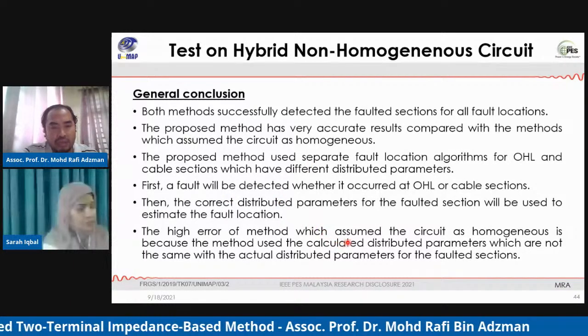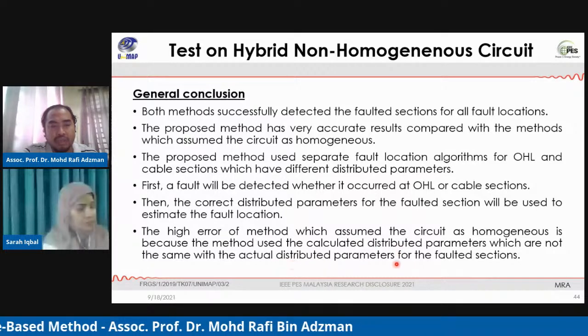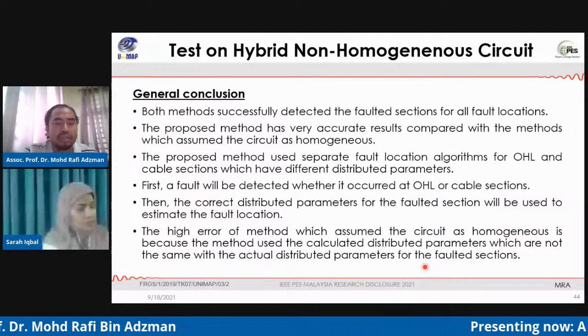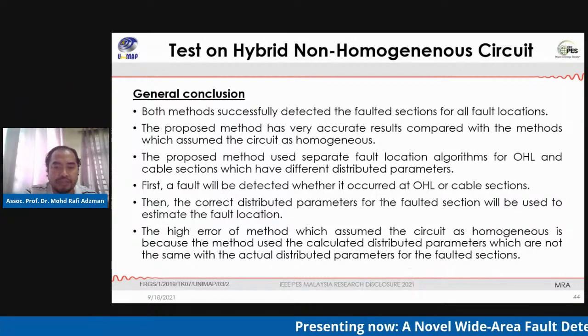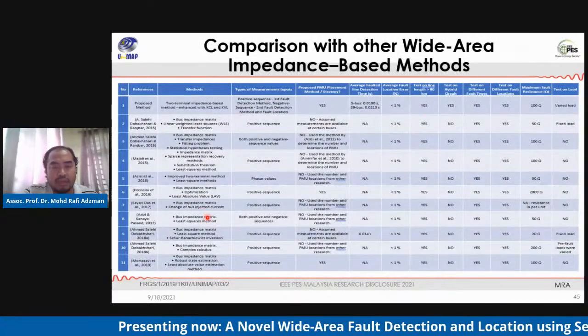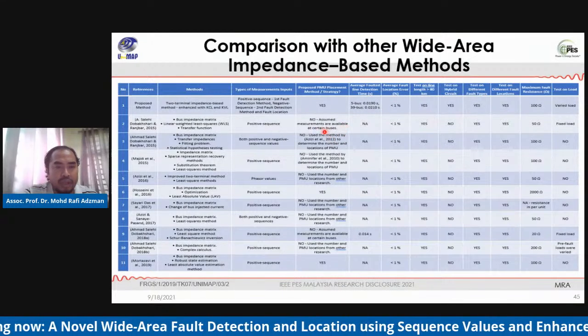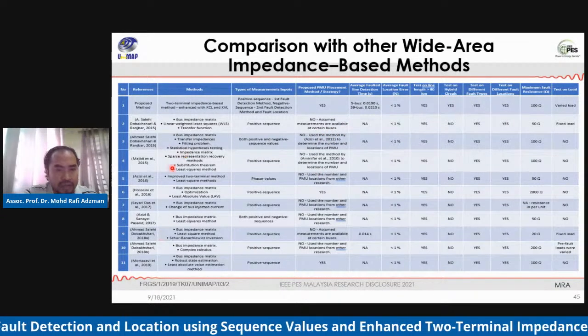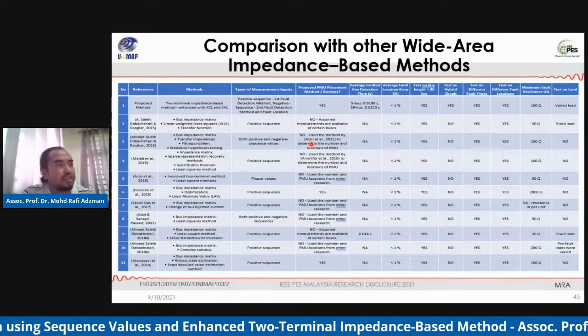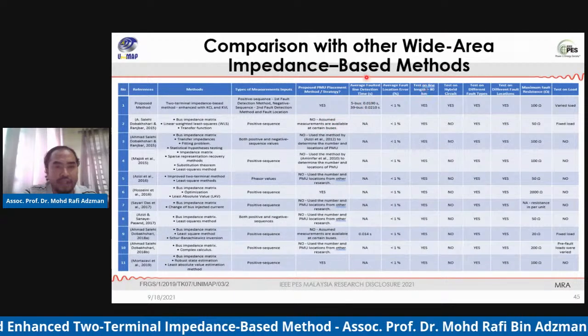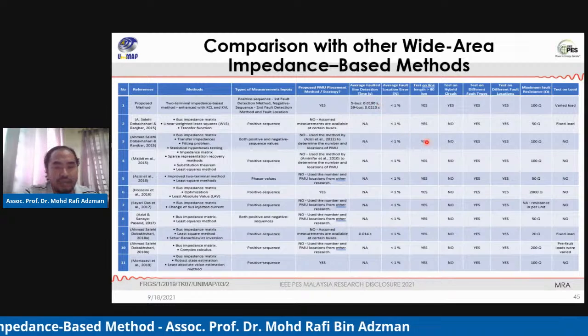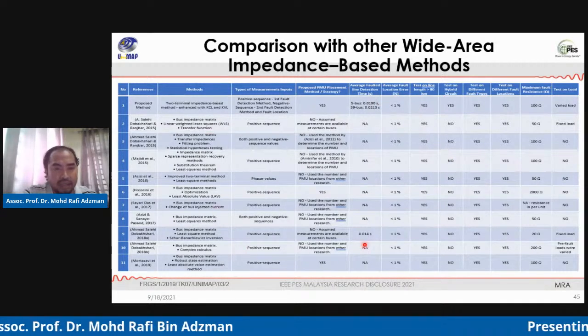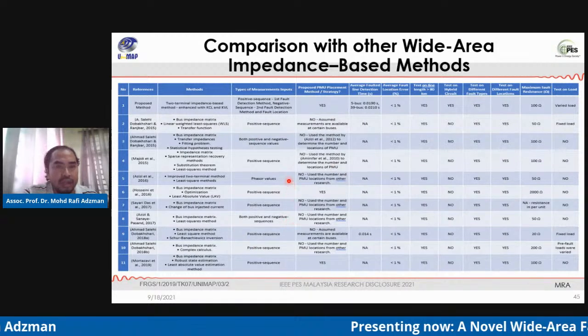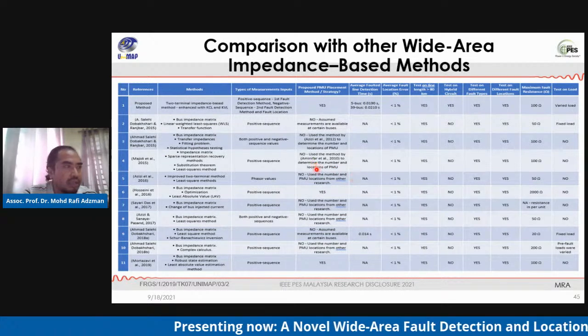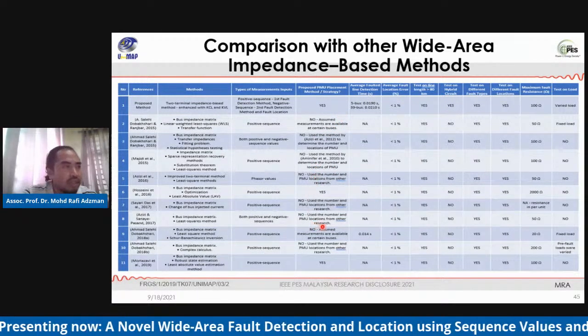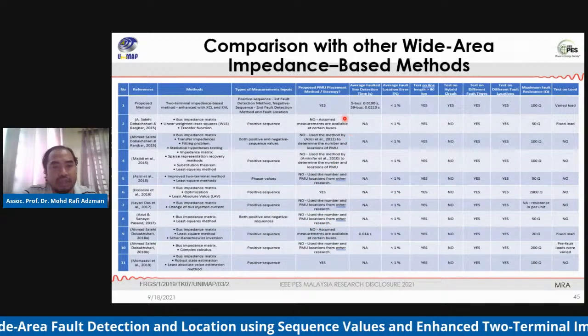The higher error of the method which assumes the circuit as homogeneous is because the method uses the calculated distributed parameter, which is not the same as the actual distributed parameter for the faulted sections. From this work, we have compared with at least 10 reference literatures, and we compare the types of measurements, the proposed type of placement, and the average faulted line detections, and we can say that it is on par with all the other researchers. Some of the researchers did not count the PMU placement strategy in their works because they assume that the measurements are available for certain buses.